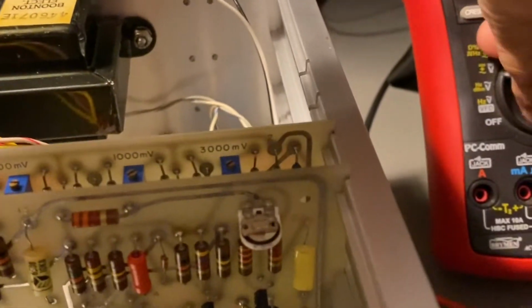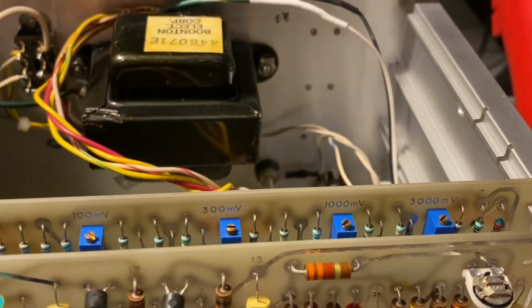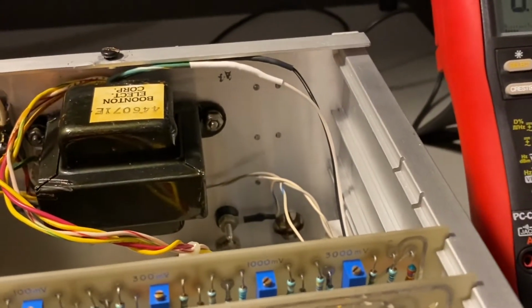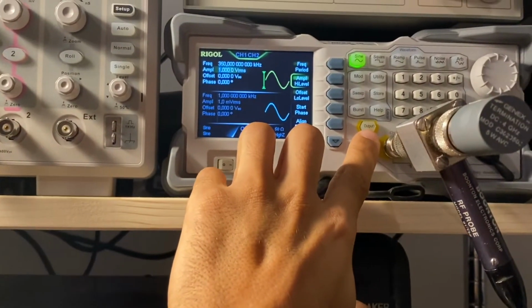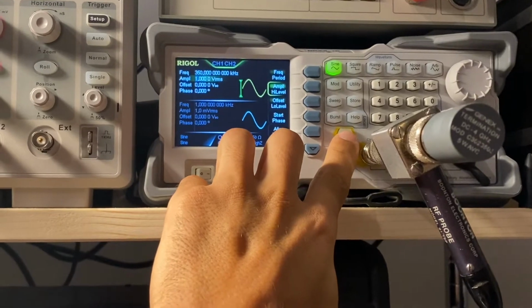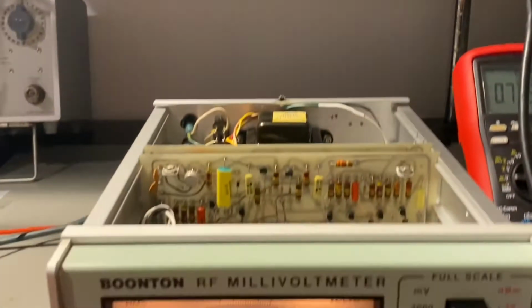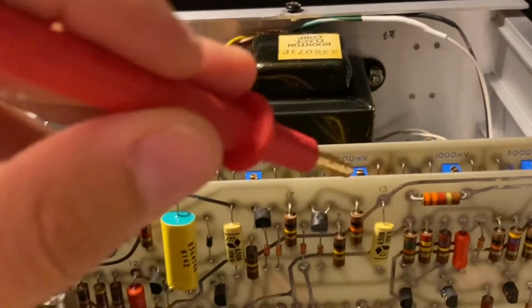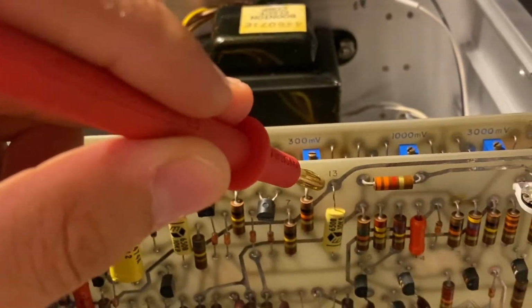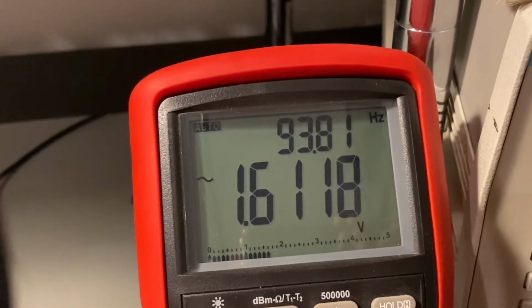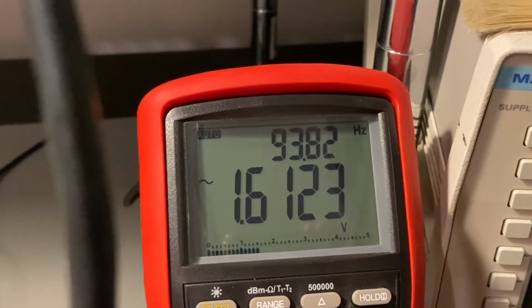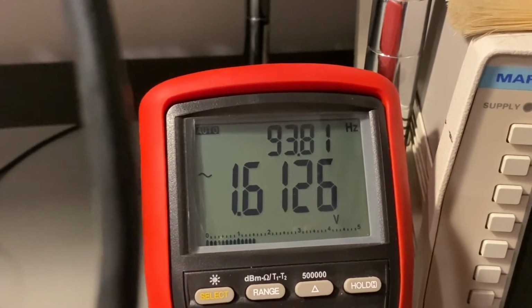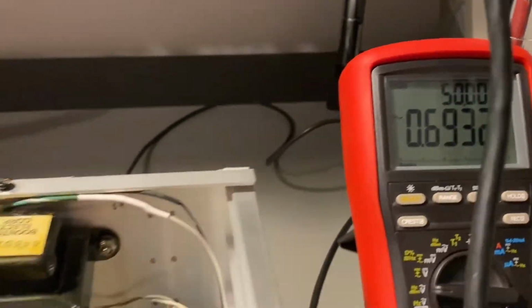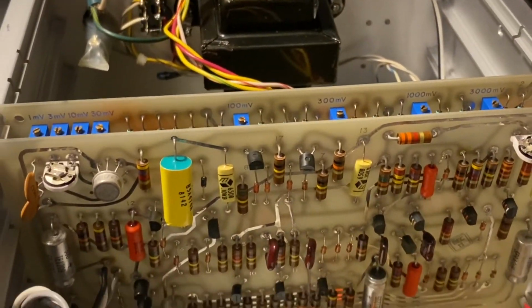So let's put the multimeter on to measure the frequency, and let's give it a 1 volt signal there. Let's put it on. We definitely have the signal. So I'm going to check here on point 13, and what we see is a frequency of 93.8. That is good enough, close enough to 94, so no problems there as well.